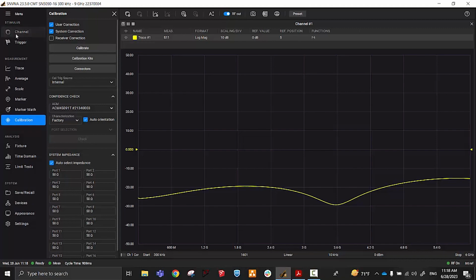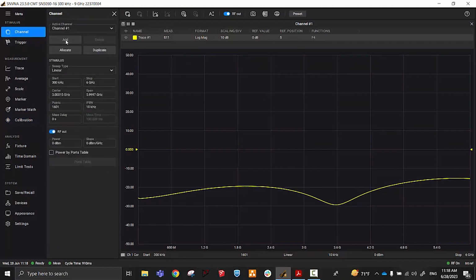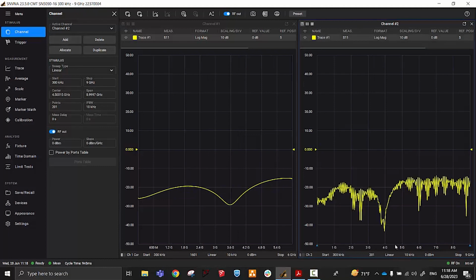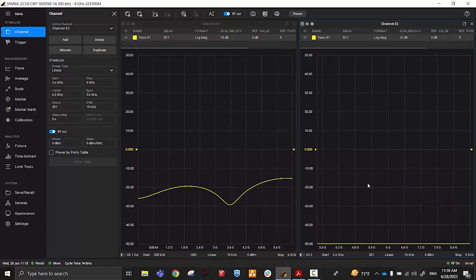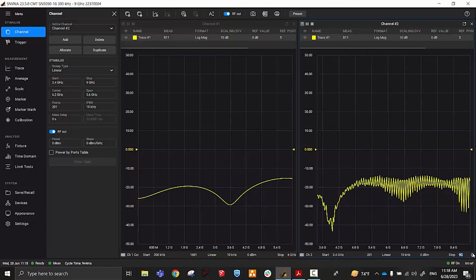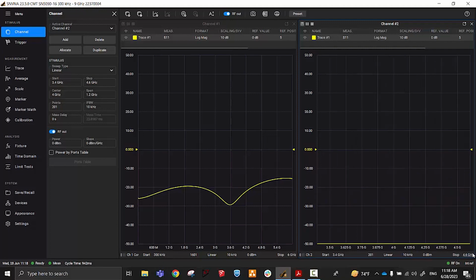Now we're going to add a new channel. And in this, we're going to do our calibration for a filter. And the filter is at about 4 gigahertz. We're going to start at 3.4 gigahertz. We're going to stop at 4.6 gigahertz. I'll have 1601 points. And we're going to use a 1 kilohertz IF bandwidth in order to have the noise floor be a little bit lower. And we're going to attach the other 2 cables, which we're going to use to measure the filter. And those are on ports 7 and 8.